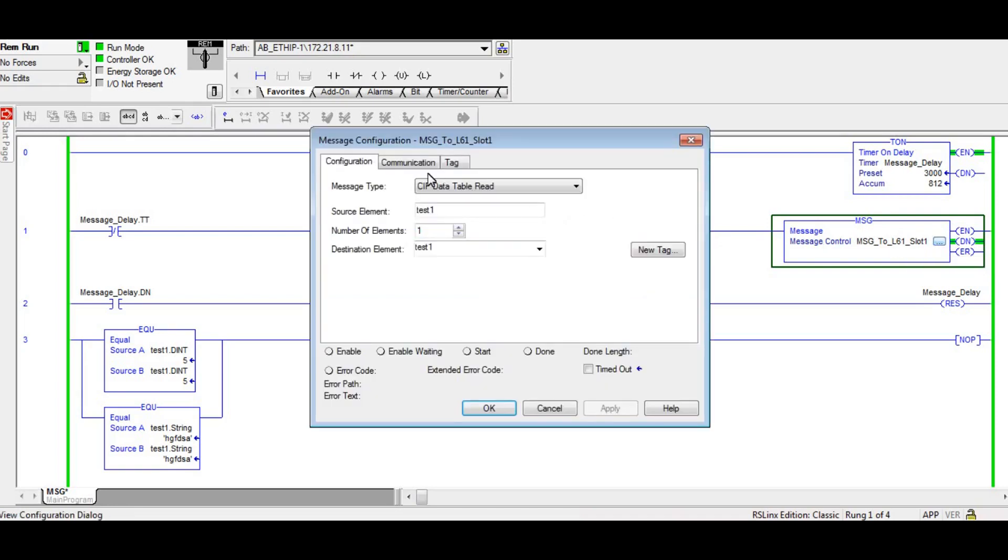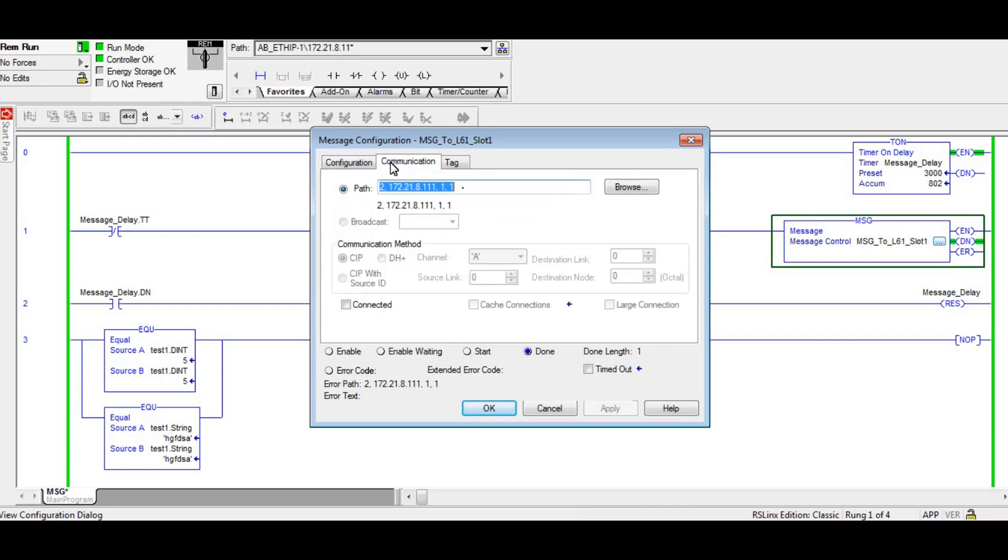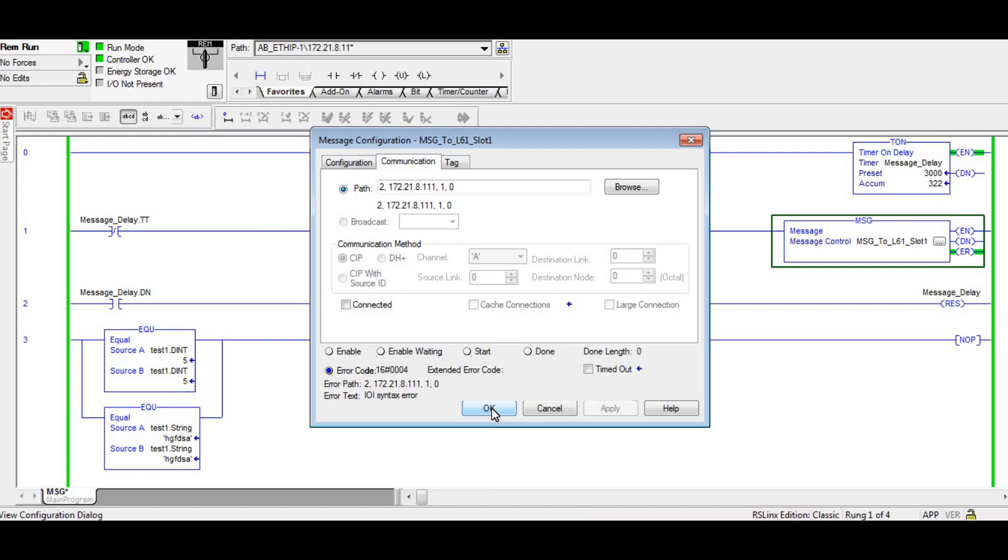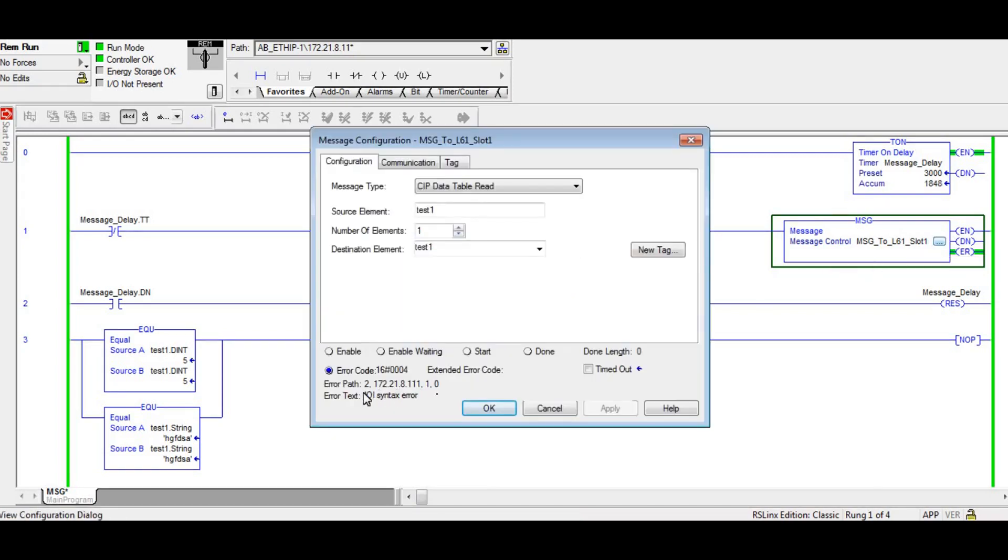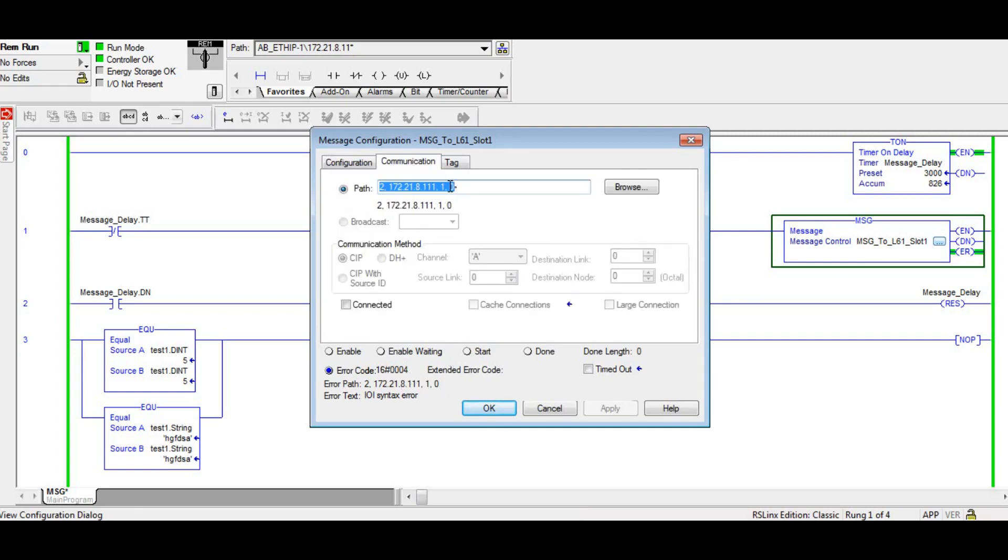What I'm going to do—and I'm reading a UDT called test one, which contains a DINT and a string, so double integer and a string, and it's one element deep, it's not an array—I'm going to change this to look at the other Control Logix PLC. And as you can see, we've errored out for a syntax error. The reason is there is no tag. The error code is not very helpful if you were to look it up. It just basically says syntax error. So let's go back to the right PLC.